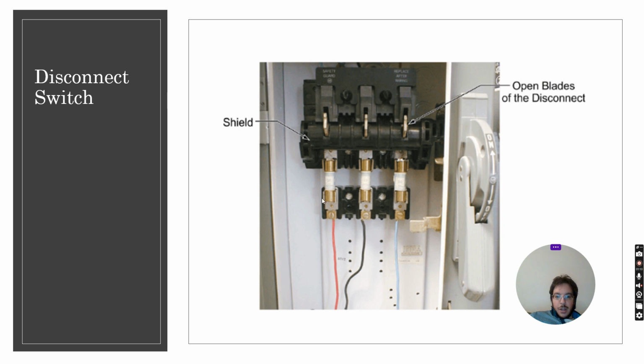Now here we've got what's called a disconnect switch. This is a fuse disconnect. It's also a 3-pole. If we look here, this has got blades, and on the right here we've got a switch, and it's in the off position. You can see on the dial it's got off and it's got on. These electrical wires go to supply. Is this a supply side, or can't tell?